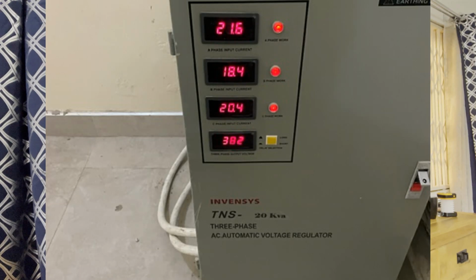It passed with flying colors. I'm showing the picture on your screen. We didn't have all the loads in the house on, but most of them, and the highest current we were registering was about 21 amps. You can see that on line 1, the first one, 21.6 amps. The second line, which was not used at all previously, was now registering about 18.4 amps.